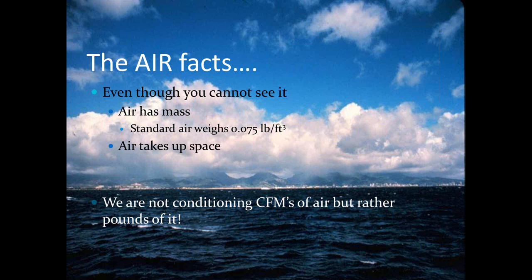Let's talk about some facts about air. Even though you can't see it, air does have mass. Standard air — at 0% relative humidity, 70°F, and atmospheric pressure of 14.69 psi — has a weight of 0.075 pounds per cubic foot. That mass or weight is basically how air transfers heat or energy.